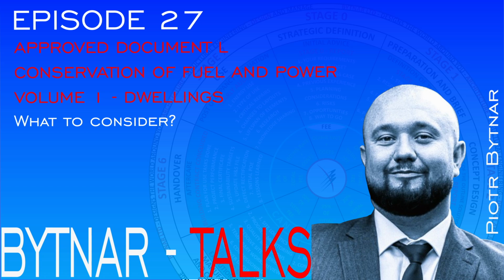Additionally, the section covers consideration for district heating, underfloor heating, mechanical ventilation, lighting, and on-site electricity generation, ensuring all systems operate efficiently and effectively within the building's overall energy framework. Section 7 mandates pressure testing for all new dwellings to ensure compliance with regulations on energy performance, specifically limiting air leakage. Tests must be conducted by certified professionals using calibrated equipment, with results submitted to building control within 7 days. Compliance is confirmed through recalculating energy, emission, and fabric efficiency rates based on the test outcomes.